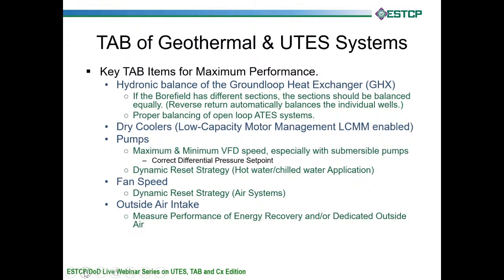Pumps, minimum and maximum VFD speed, that's something the TAB contractor has to set up, especially with submersible pumps. Submersible pumps are a little different. We'll talk about that later on too. They're a little different than traditional centrifugal pumps that are in suction or inline pumps, in that they can't turn down to 25 or 30%. They can only turn down to 50%. So if a TAB contractor doesn't know that, he needs to be aware of that.